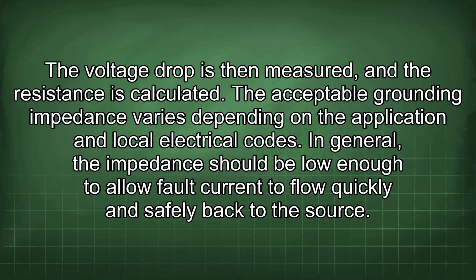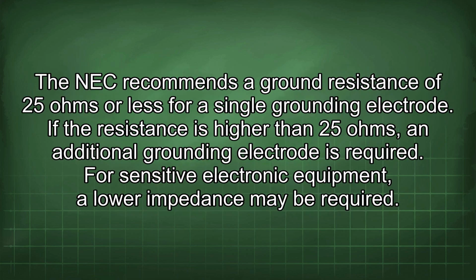The acceptable grounding impedance varies depending on the application and local electrical codes. In general, the impedance should be low enough to allow fault current to flow quickly and safely back to the source. The NEC recommends a ground resistance of 25 ohms or less for a single grounding electrode. If the resistance is higher than 25 ohms, an additional grounding electrode is required. For sensitive electronic equipment, a lower impedance may be required.